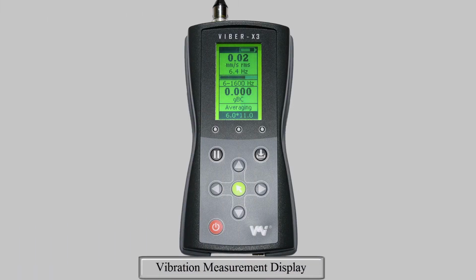At the bottom of the digital display, your selected alarm levels are shown. On the left is warning, and to the right danger. They are separated by a star in the middle. When your measurement is between the set warning and danger limits, the orange LED will light. If the measurement exceeds the set danger limit, the red LED will light. When taking a vibration measurement, ensure good contact between your accelerometer and the measurement point. Observe the stability bar and measurement status, and ensure they are both stable before recording your measurement.